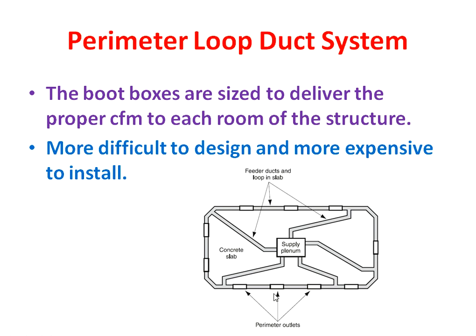Boot boxes are sized to deliver the proper airflow to each room. The function of boot boxes is to control the flow of air and CFM in the room. This system is more difficult to design and more expensive to install, because it is always constructed inside the concrete slab, making construction more complicated and costly compared to other supply duct systems.